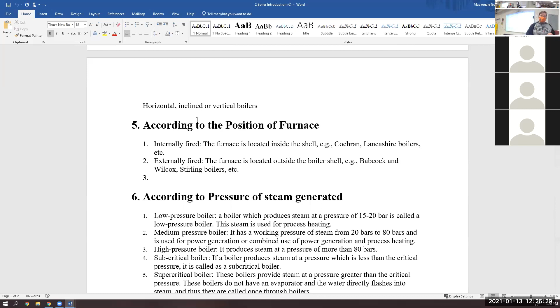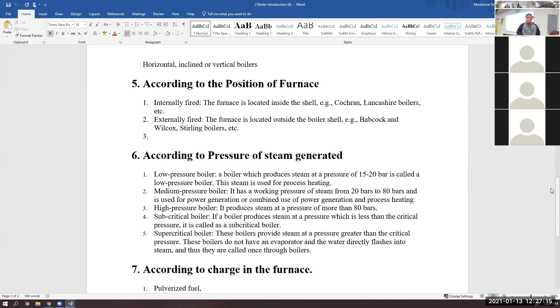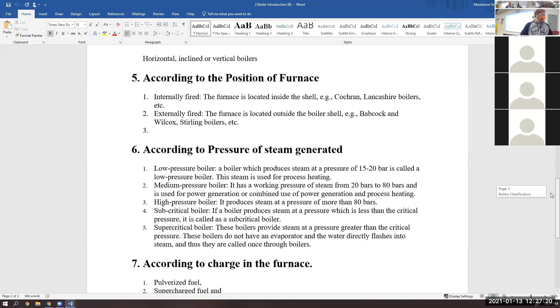Whatever arrangement you have, you can also arrange the position of the furnace that creates heat from the fuel that then heats the water. You can put your furnace inside the shell — the most common type of this is the Lancashire boiler. Or you can put it outside the boiler, where you have combustion and then transport that hot combustion gas to your boiler shell. Babcock and Wilcox is the most common brand you see of that. They're a huge company in energy production, and they manufacture a lot of components for power plants.